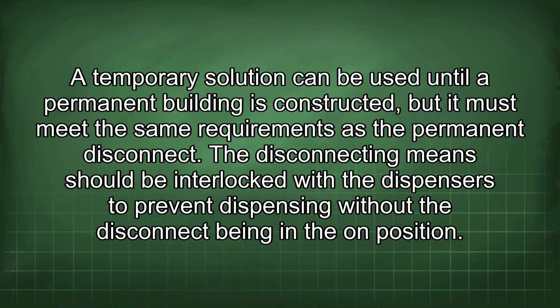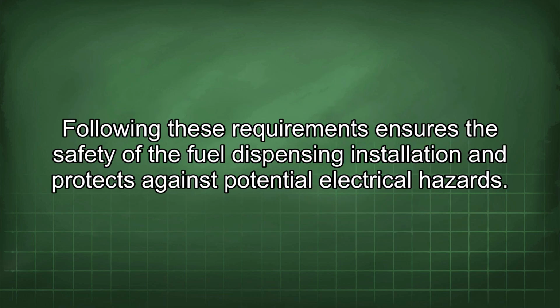The disconnecting means should be interlocked with the dispensers to prevent dispensing without the disconnect being in the on position. Following these requirements ensures the safety of the fuel dispensing installation and protects against potential electrical hazards.